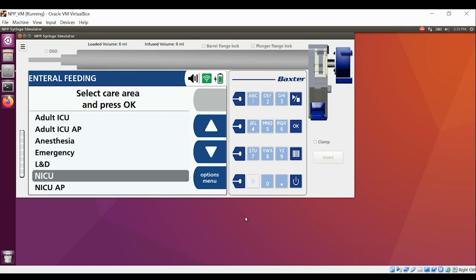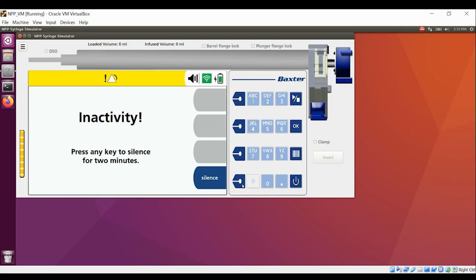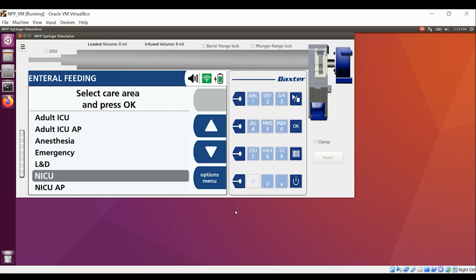Some concerns within the NICU. We talked about stiction, which is common in all syringe pumps. Another thing is vertical displacement. When you are moving a syringe pump around, when you increase the distance between the catheter tip and the pump, raise it up, you could potentially bolus the medication to the patient. And conversely, when you drop it below the patient's IV catheter, you could slow down the infusion. So it's important to point this out to clinicians that whenever they are either moving the patient or moving the syringe pump, they need to clamp the line so that when they're moving the patient around, there's not an issue with either bolusing or causing an interruption in flow because of that movement.